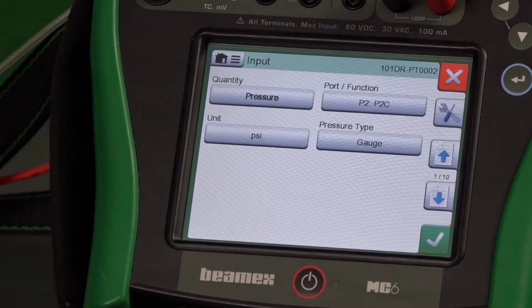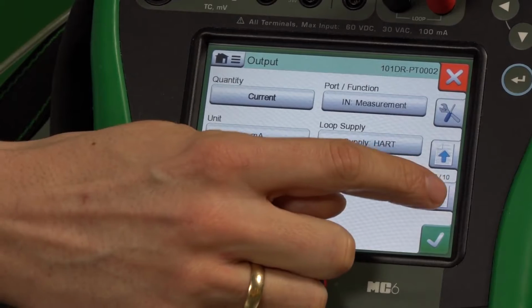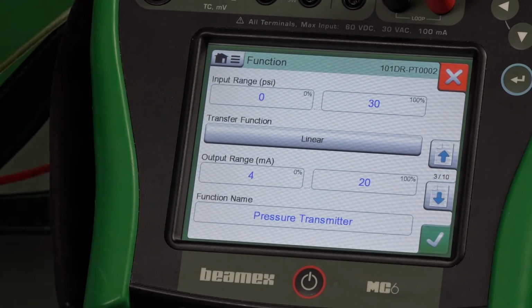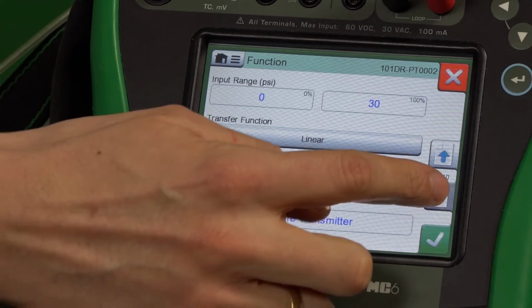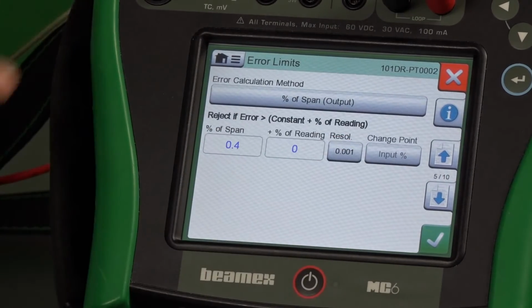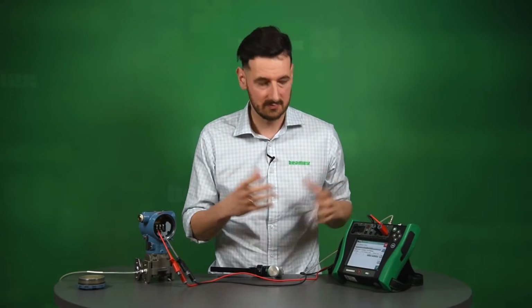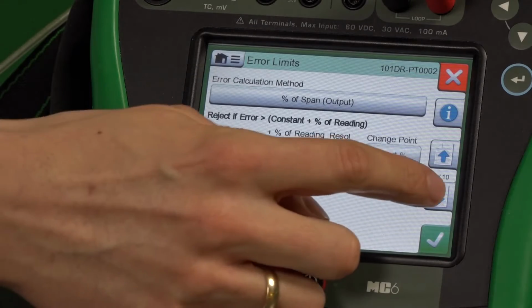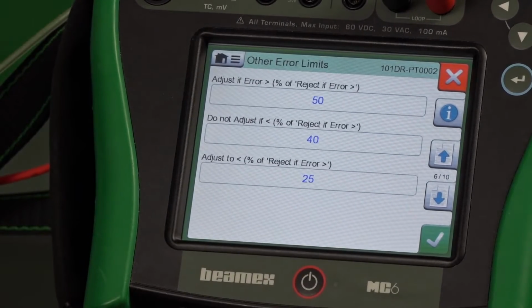But before I jump there, let me just quickly show you what else we set up here. The range is obviously 0 to 30 psi. It's 4 to 20 on the output. That's what we said. We also set up that this transmitter should be within 0.4% of span tolerance. Of course, that could be changed, but this is what we decided for this transmitter.